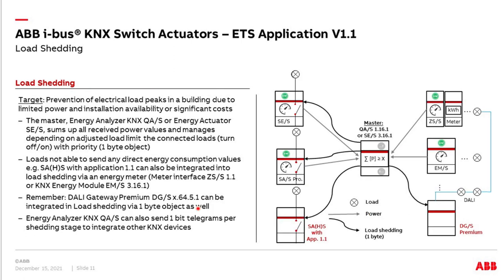Let's look at load shedding in detail. Before we come to the changes, a small update on what load shedding is. Practically it's a prevention of electrical load peaks in a building due to limited power, installation availability, or significant costs if you overshoot a certain power level. The target is to turn off loads with different priorities in order not to exceed a certain power level. A so-called master provides the intelligence in this logic.